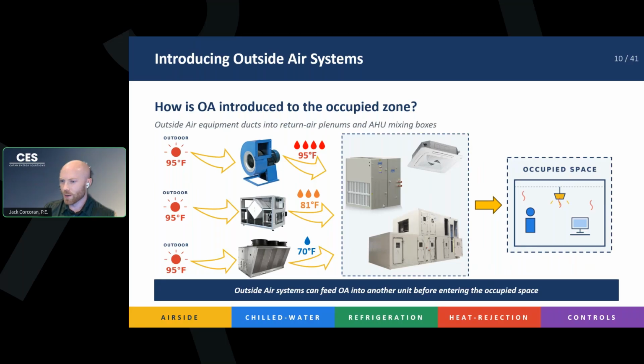It's the same situation for our ERV. In this situation, however, we can downsize the unit that's in the box. Maybe you don't need as big of a coil because you don't have 95-degree wet air coming over it. You have 81-degree and slightly less wet air coming over it. And then the last thing is your DOAS unit. This already has a coil. We're already putting in work. So that means we're going to be able to downsize that indoor unit in the occupied space as much as possible. That unit isn't going to have to do much lifting. All it has to do is temper the return air that's coming in and mixing with this 70-degree air. But as we said, the two ways to provide your outside air into your occupied zone are directly into the space, or mixing it with return air into a downstream coil.